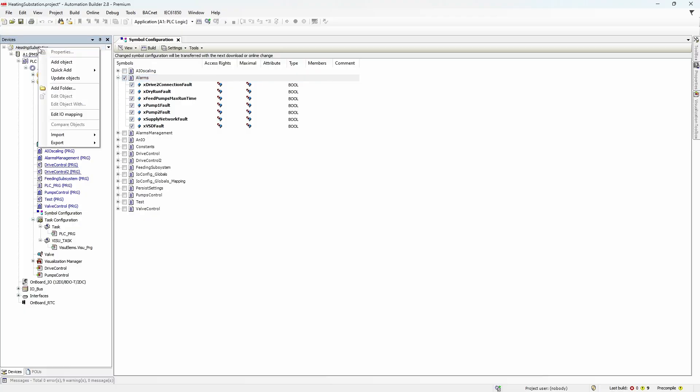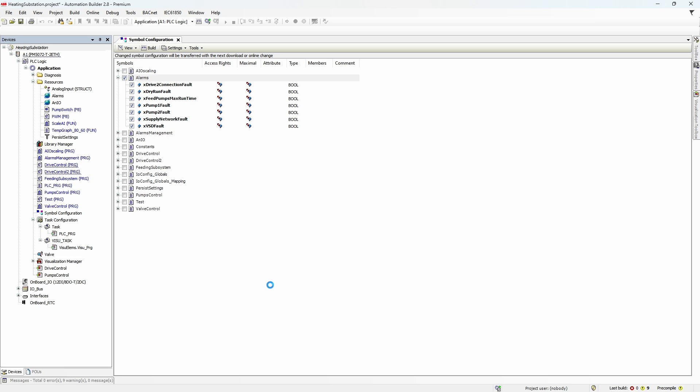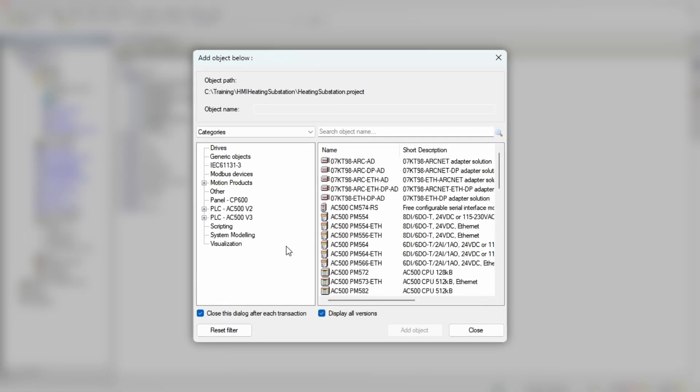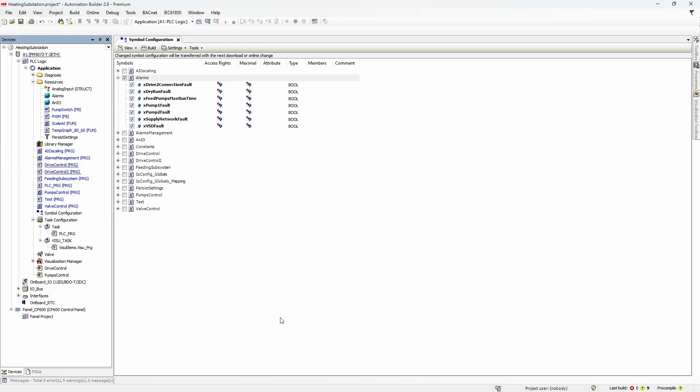There are actually two ways to connect the HMI and PLC projects. You can right-click on the root element in the project tree, press Add Object, and find the panel CP600 element. Then if you double-click the panel project item, you'll be redirected to the HMI part and start with project creation. This approach will work and you can absolutely use it, but I want to show you a slightly different one where you have more control.